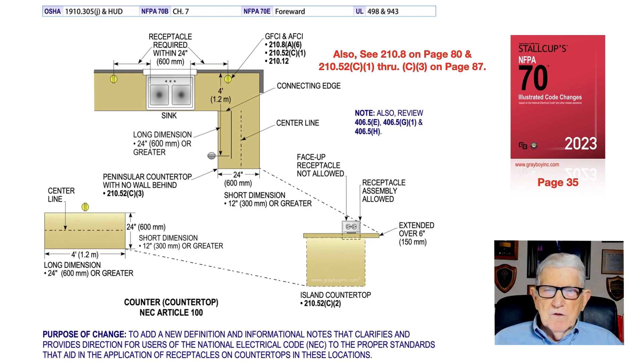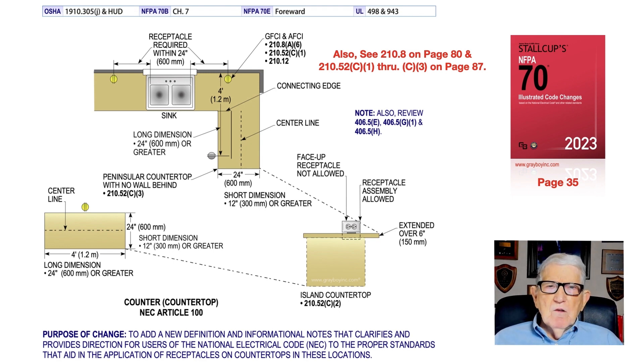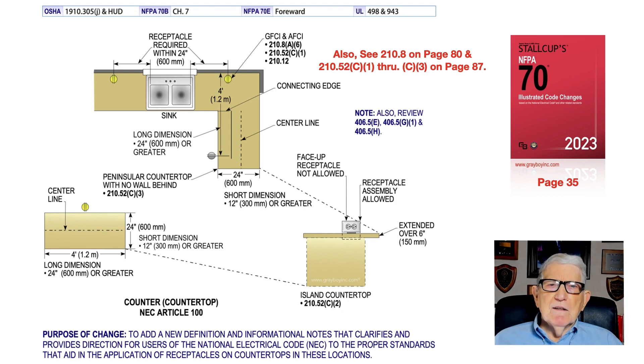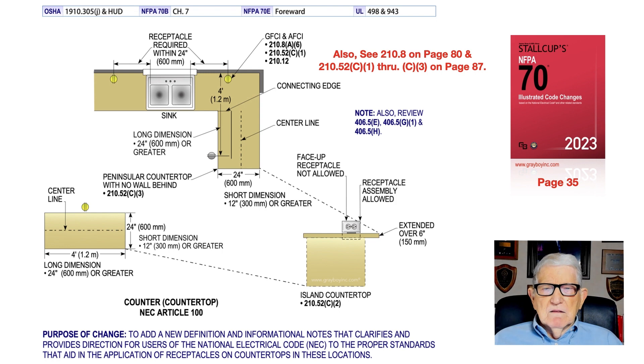This illustration deals with countertops in accordance with NEC Article 100, approximately page 35. You should review 210.52 C1 through C3 on page 87 to see where receptacles are required to be installed. For GFCI protection, see 210.8A for dwelling units and 210.8B for other locations, on page 80. This new definition was added to define a countertop — which has a wall behind it — a peninsula — which has no wall but connects to a countertop — and an island.